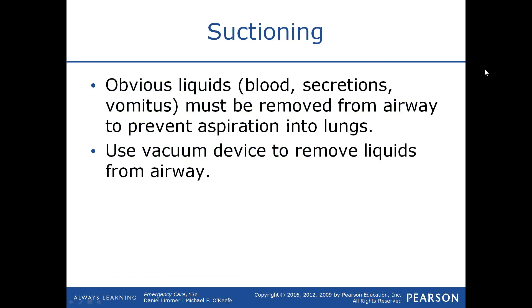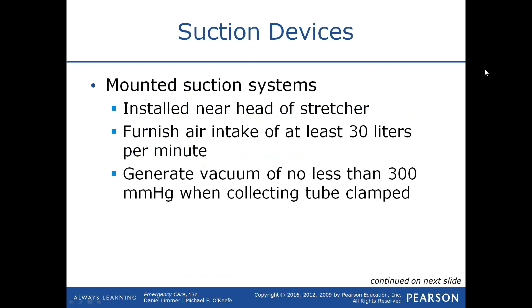You can use a vacuum device or a suction device to remove liquids from the airway. And there are different types of suction devices out there. There's the mounted suction systems that you'll see in the back of the ambulances or mounted on the walls in hospital emergency departments. They're able to furnish air intake of at least 30 liters per minute and generate a vacuum no less than 300 millimeters of mercury. You'll notice when doing your clinical and ride, you can adjust the millimeters of mercury of suction that the suction unit provides, but typically 300 is what you want for an adult. That may be a little too much for smaller children.